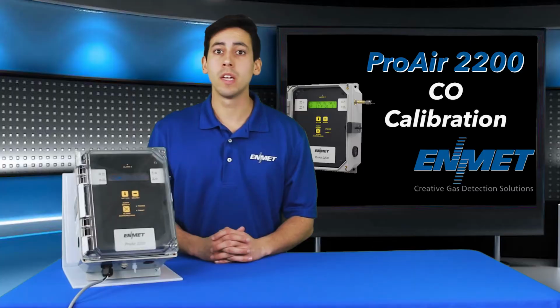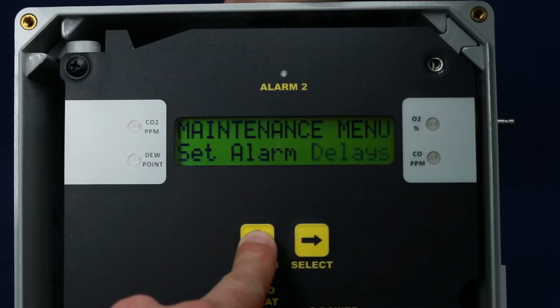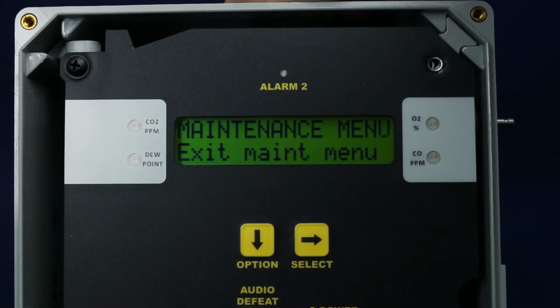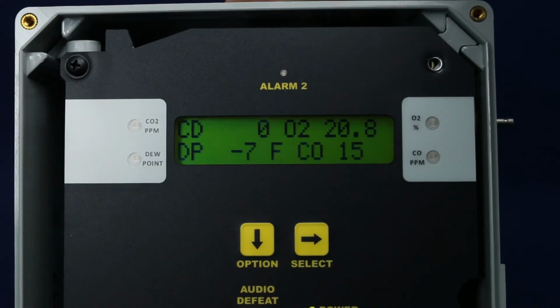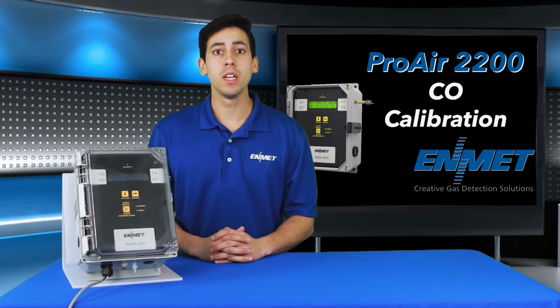Maintenance menu. Press the Option key until Exit Maintenance Menu appears on the display. Then press the Select key to return the instrument to the operational display. You may reattach your compressed air to the ProAir 2200. This completes the ProAir 2200 calibration for the CO channel.